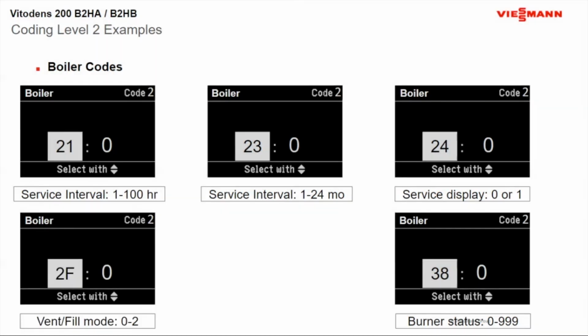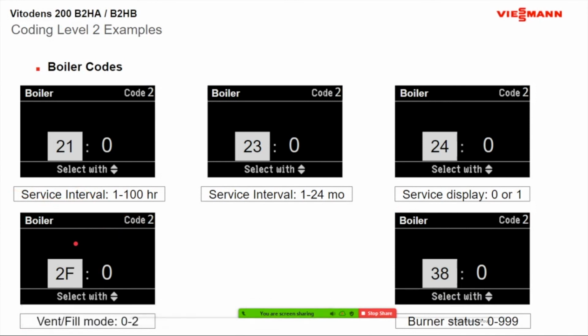And remember the 2F at the bottom here, that's that fill mode. So you can go there as well. But I would go right into the service menu and not even go into coding, because you can go right down to that service function and go right to that fill mode or vent mode. So you don't have to go into coding.